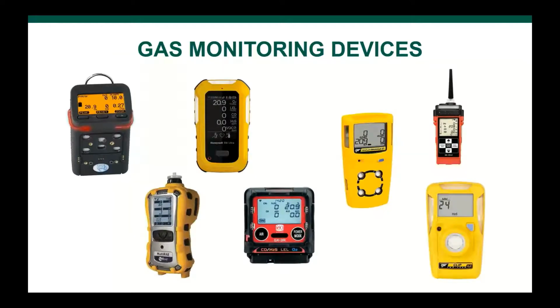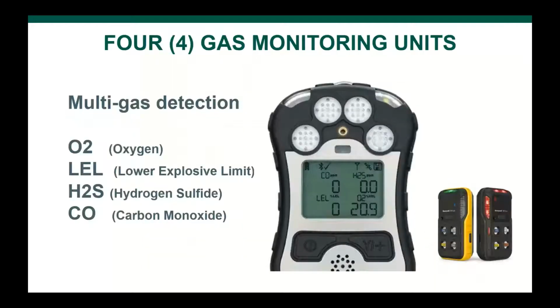There's a lot of monitoring devices out in the market. So it's very difficult that you won't be able to find a piece of equipment that is going to do the job. As you can see, there are multiple gases: 2, 3, 1, 4 gases. My personal opinion, I would never use a one gas monitor. I always would use at least the most common tool that is used in confined spaces, the 4-gas monitor that will check for oxygen, the lower explosive limit, hydrogen sulfide, and carbon monoxide.